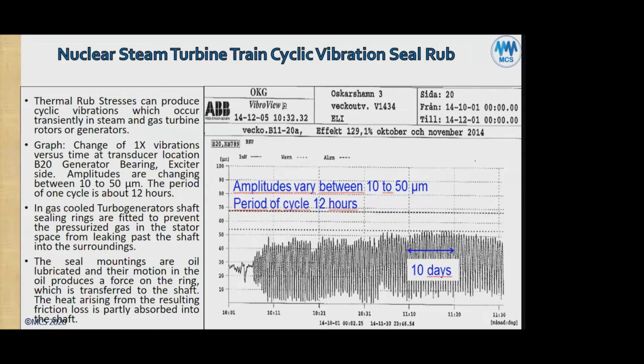Here we have a next example, a nuclear steam turbine generation unit. It's the generator itself. They suspected it had a seal rub because they were getting a variation in vibration on the bearings. As you can see, the amplitude varies. The smoothest is almost maybe 5 micron, and it's going up to a max of around 50 micron. So really going from 5 micron up to 50 micron, which is something like 2 mils, almost 40 micron, which is 1 and 3/4 mils approximately, in a period of 12 hours.